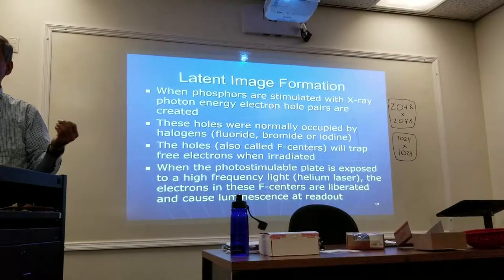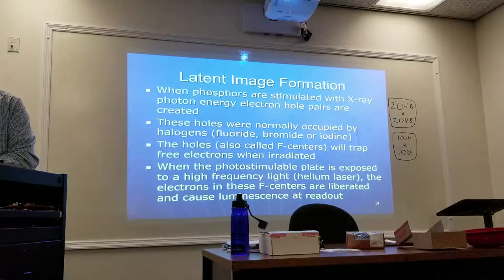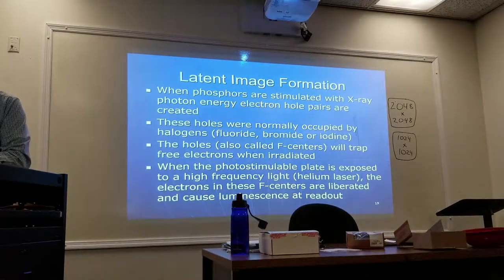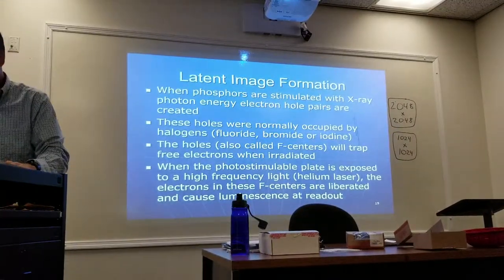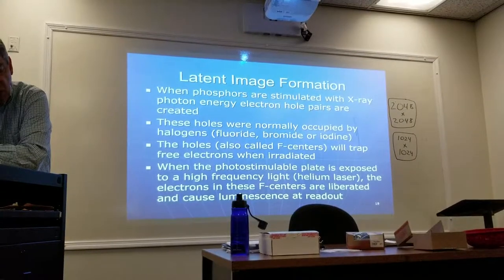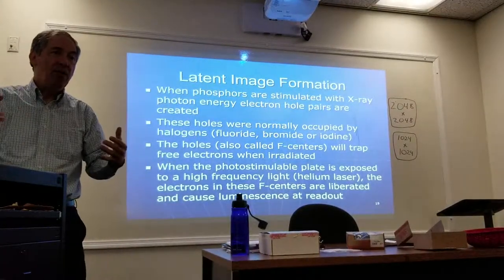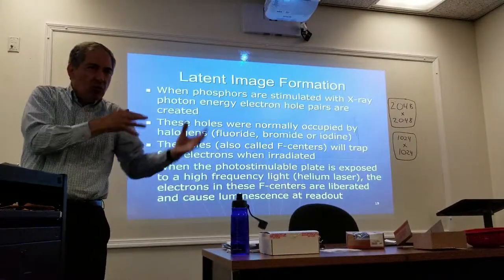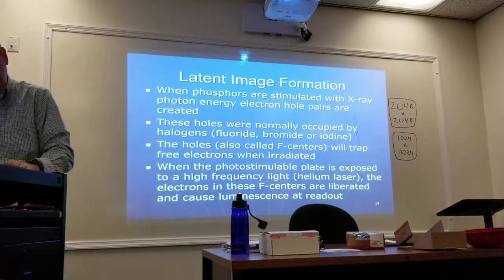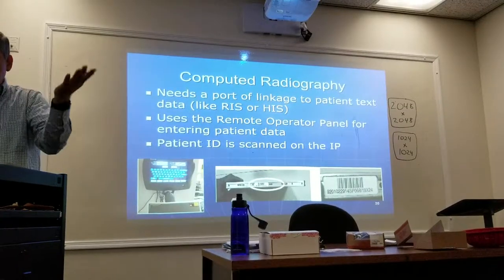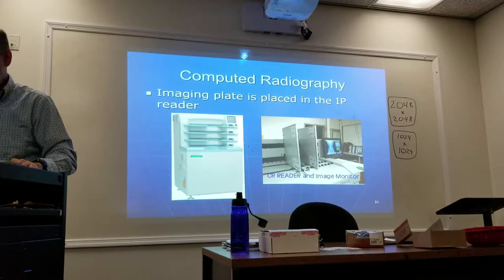When the phosphors are stimulated with an x-ray photon, electron holes are created — also called F-centers — and they trap the free electrons when irradiated. Then when the plate is exposed to laser light, the electrons are liberated and give off light, which is the signal. The photostimulable phosphors, when trapped, are in a higher energy metastable state — they can't hold that energy, so they want to be released, and that's what the laser light does.